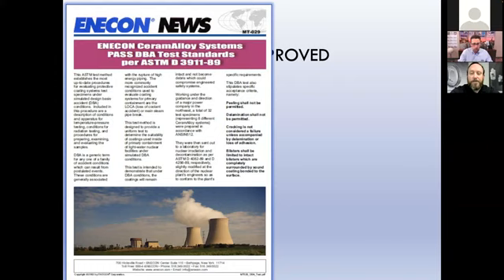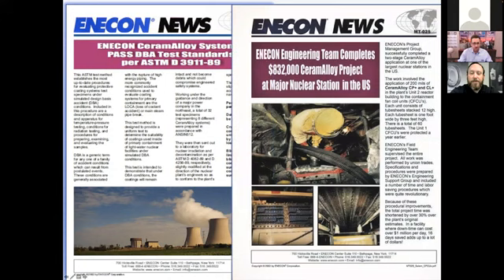In the event of a LOCA, which is a loss of coolant accident, the products cannot prevent the safe shutdown of the plant. Therefore, the products are tested to make sure they cannot peel off, flake, or delaminate while the plant is being shut down safely. Our systems have passed this test, and ENECON has been providing nuclear stations with critical protection for safety-related heat exchangers for well over 30 years. This application is at a Mid-Atlantic nuclear station on their containment fan coil units. This series of heat exchangers is used to cool the primary containment and the equipment inside.